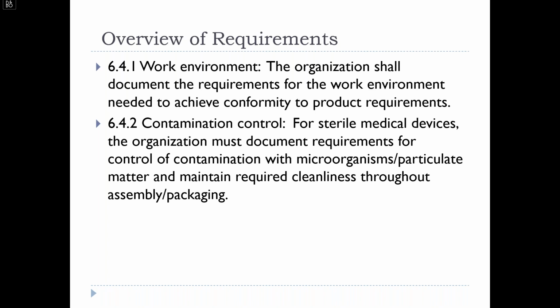6.4.2, contamination control. For sterile medical devices, the organization needs to document requirements for control of contamination with microorganisms or particulate matter and maintain that required cleanliness throughout assembly and packaging. So you're seeing here a trend, lots of requirements for documenting, documented procedure, documented requirements, documented specifications, much more above and beyond 9001:2015.